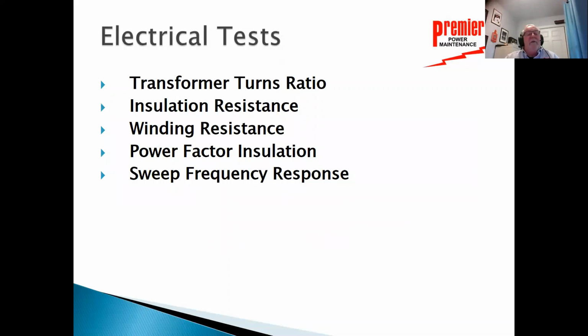The electrical tests on a transformer are basically the turns ratio; the insulation resistance, to make sure that the paper and the oil are good; and winding resistance, to make sure that we haven't had a reforming of coil and coil assemblies. A power factor insulation test is the first test we can do that will actually look at the paper insulation as well as the oil itself. And then a sweep frequency response test will tell me if things have changed in any portion of the transformer during a fault. It will tell you if there's been some buckling of the transformer winding, even if all the other tests come back correct.